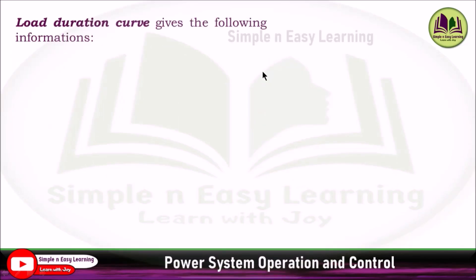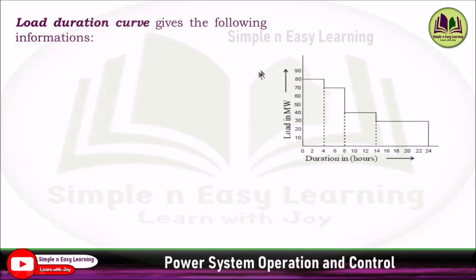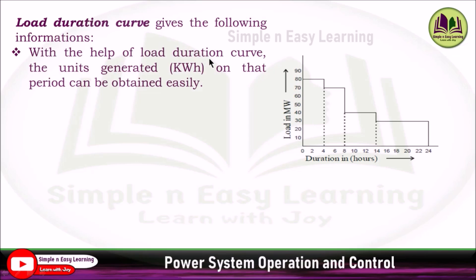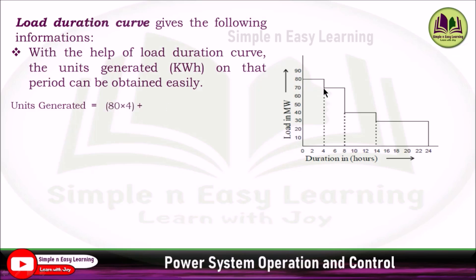The load duration curve gives the following information. With the help of the load duration curve, the units generated in a particular period can be obtained easily. For example, in this load duration curve the maximum demand is 80 megawatt for 4 hours, so units generated equal 80 × 4. The next is 70 megawatt for 4 hours.